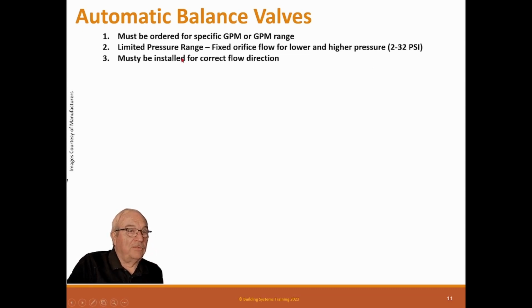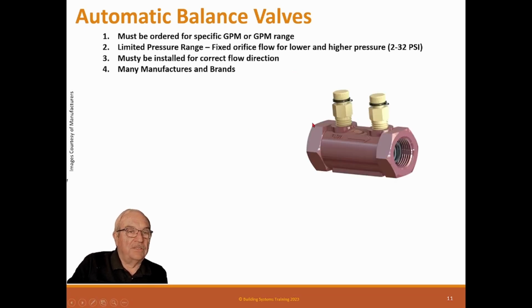It must be installed for the correct flow direction. Yeah, you can't install it backwards. It won't work at all. There are many manufacturers, many brands. It used to be there were only 3 or 4 manufacturers of these, and now there are tons of them. This is a simple one. It's just a piece of pipe with a single plunger in there. It's probably a half-inch one. And you measure across here.